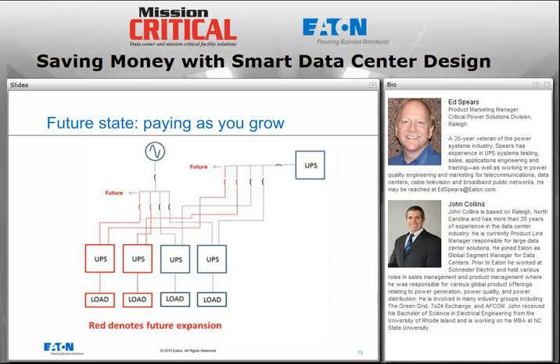So one of the things that this picture shows us is a system where on day one they might have bought two different UPSs that are shown here in blue, but they knew they're going to expand, so they arranged their switchgear with compartments that allow them to rack in or add different size breakers and additional breakers down the road to feed the bypass and the catcher inputs of both the original UPSs and any subsequent UPSs that they need. But it's very hard to predict what they will need on day one. But you see, with this type of system, you can decide, okay, I'll have a certain size breaker in year two. Once year two arrives and I know what I need, I can populate it with the appropriate size breaker and put in a UPS here shown in red that's not any bigger than it has to be at that time. It might be a large UPS. It might be a very small UPS. Doesn't matter. They all work together in a smart catcher system. And then as I continue to grow, maybe I need the fourth UPS.